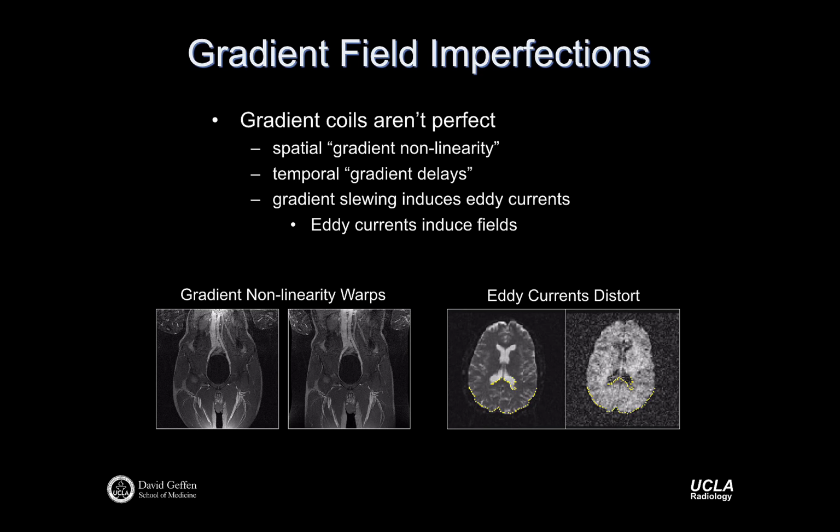And we assume, in general, a linear mapping between position and frequency. You can see today already that we can manipulate frequency now, right? We can turn on gradients and we can manipulate the Larmor frequency. And so you can start to get this idea that, okay, if that spins at a particular frequency, it's starting to tell me what its position is. And that was kind of the real insight that Lauterbur and Mansfield had, that you could encode spatial information by manipulating the range of frequencies, what we learn about in Fourier imaging later.